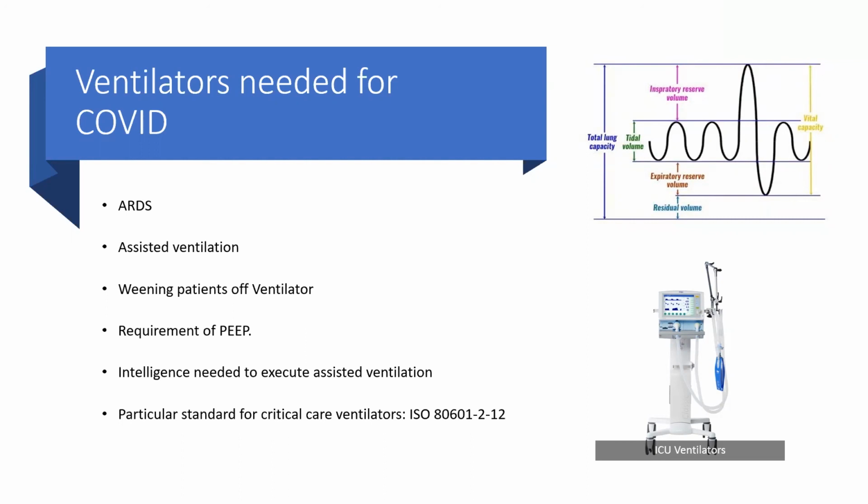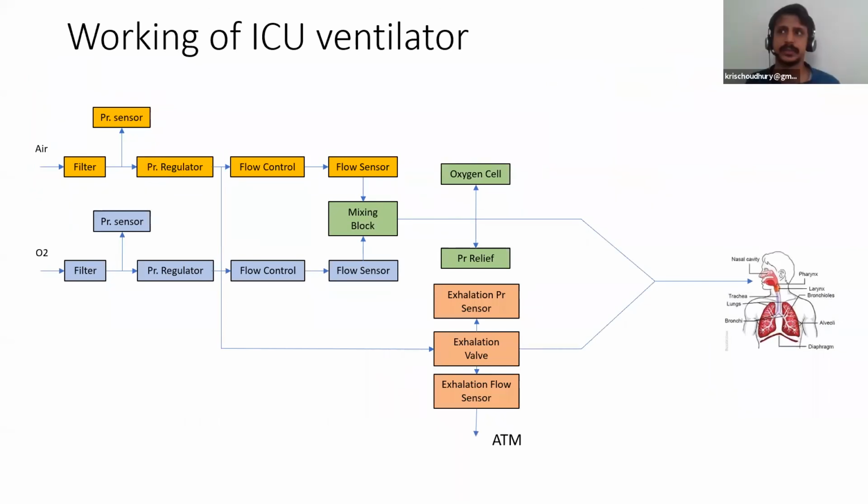Do we usually have lung simulators in educational hospitals? I don't think so, because it's a very expensive piece of equipment. Most people think test lungs are lung simulators, but they're not. A lung simulator is a machine that can easily cost upwards of 10 lakh rupees. And it's very difficult to maintain because you have to send it out every year to calibrate to the US or to whomsoever is the manufacturer of the simulator. They calibrate it and then send it back, year on year. It's very expensive to keep and very expensive to maintain as well.